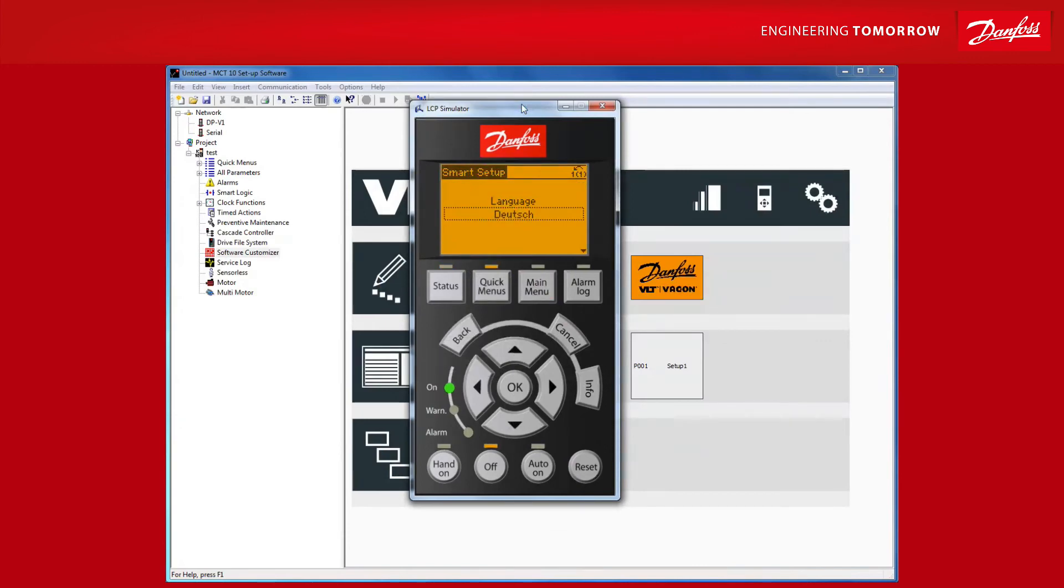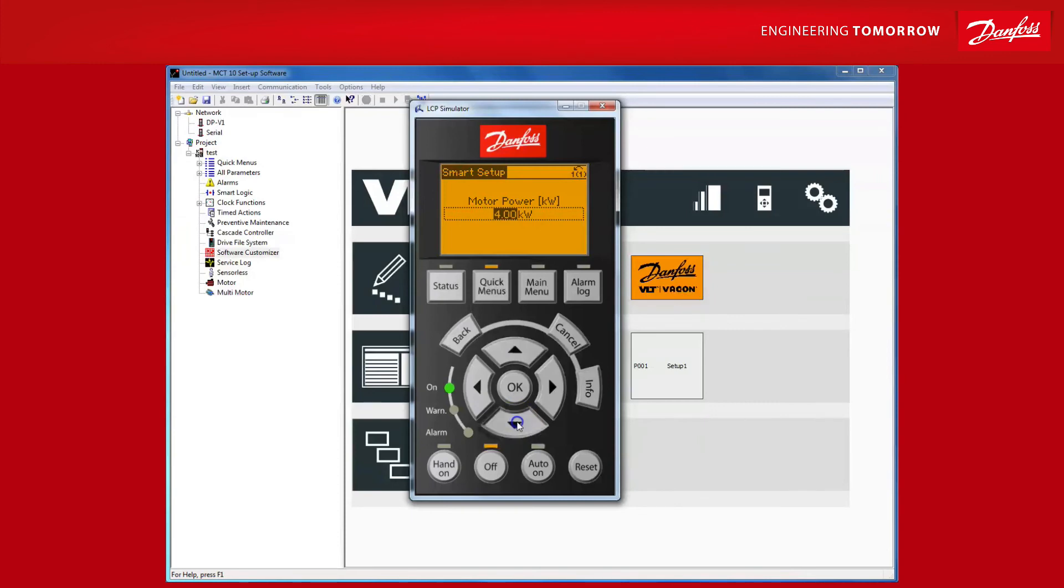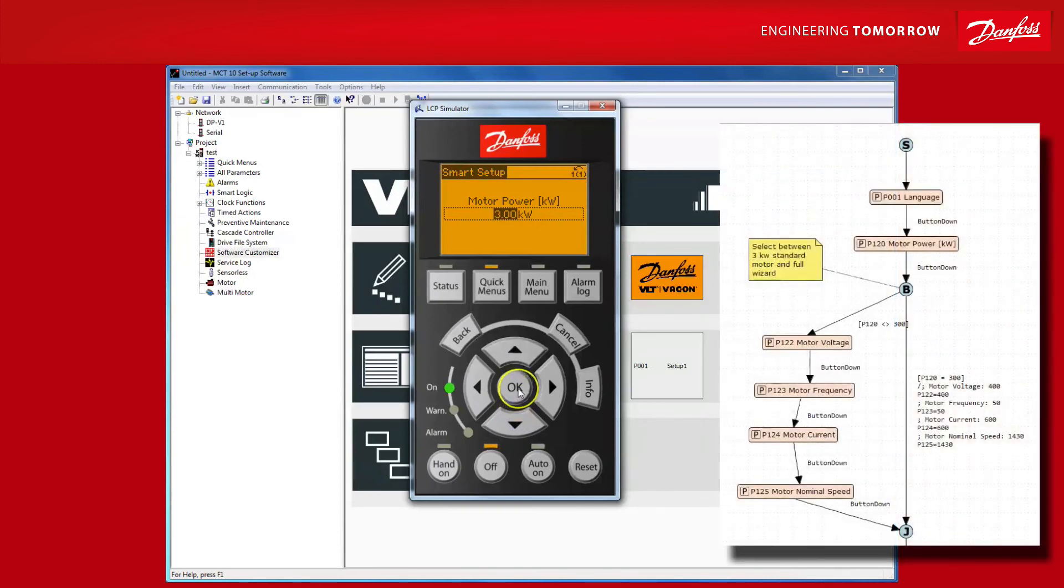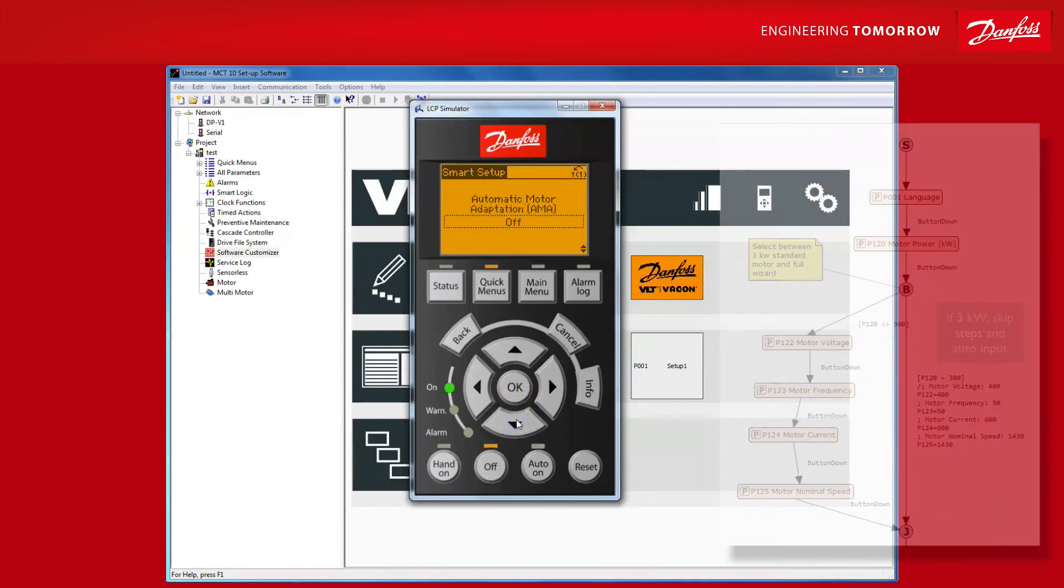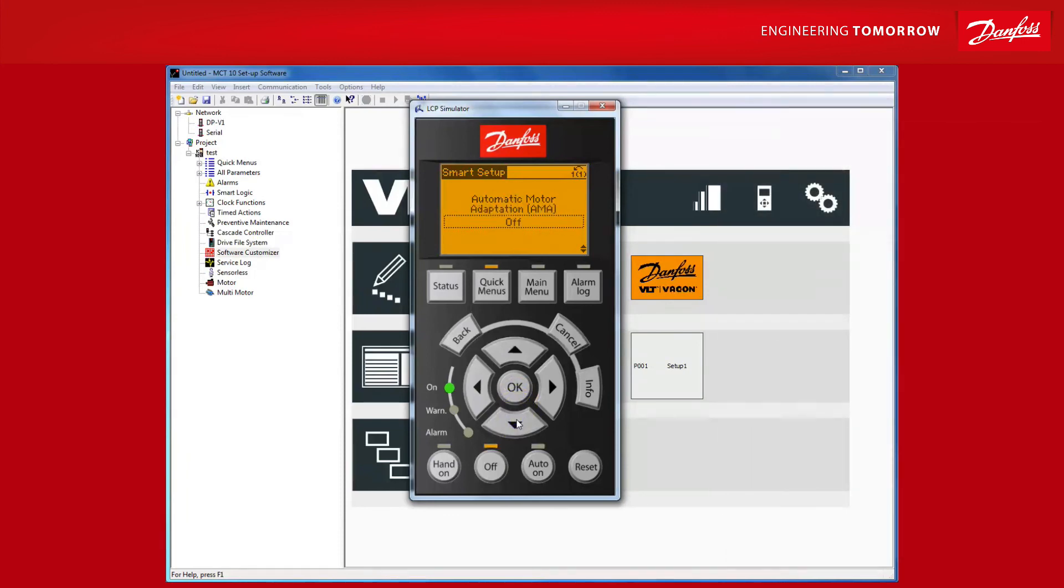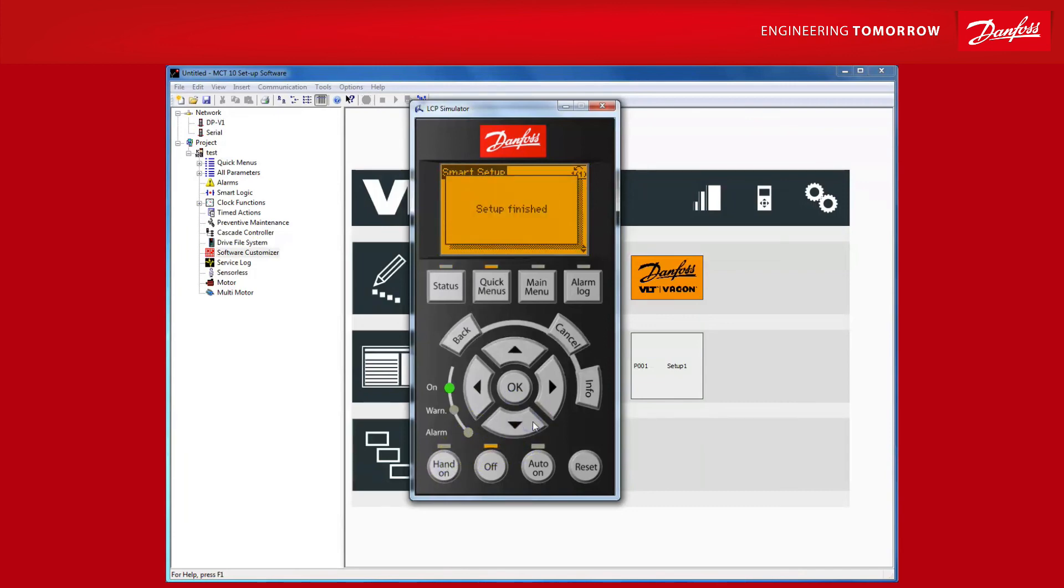Next, the SmartStart wizard kicks in. And if you remember, we changed the initial value of the display language to German. But just as programmed, the display is prompting us for the language. So let's go back to English. Next is the motor power. Now, in order to showcase the wizard, let's input 3kW so that our standard 3kW motor that I talked to you about with the wizard already has all the motor data. So it should skip the steps, automatically input the values. And of course, it does and it directly prompts us for the AMA, which we are certainly going to perform. Hit hand on, AMA complete, and setup has finished.